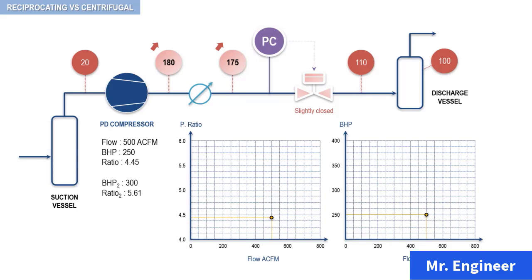This new ratio is equal to 5.61. Now, let's plot these two points on the two graphs: the new pressure ratio as a function of the flow, and the new brake horsepower as a function of the actual flow. Notice here that both the pressure ratio and brake horsepower curves are essentially a vertical line.